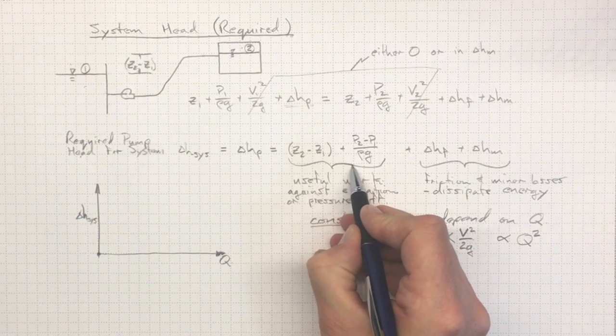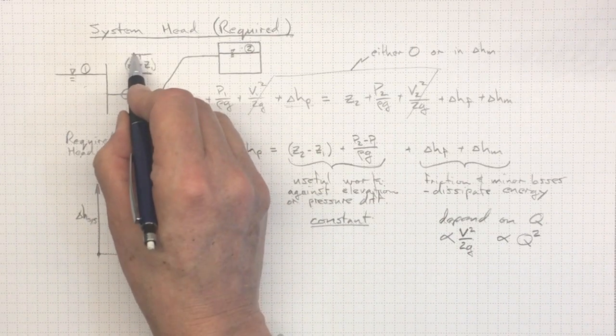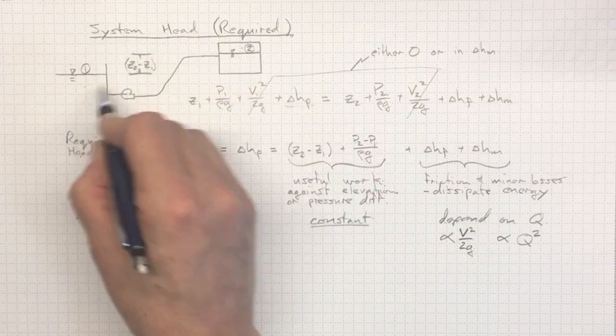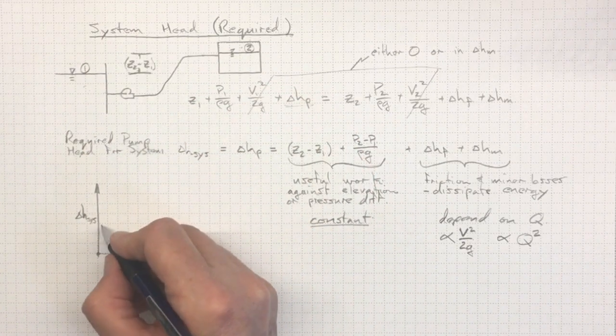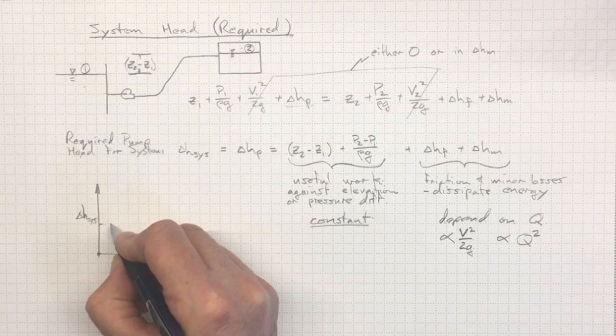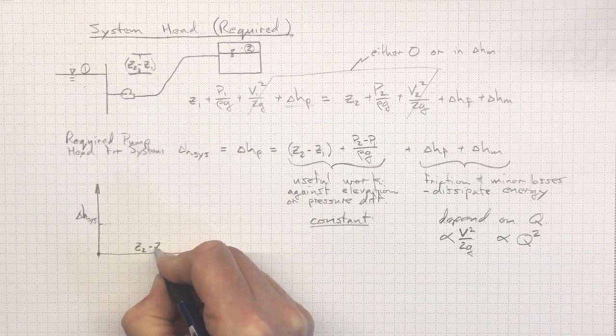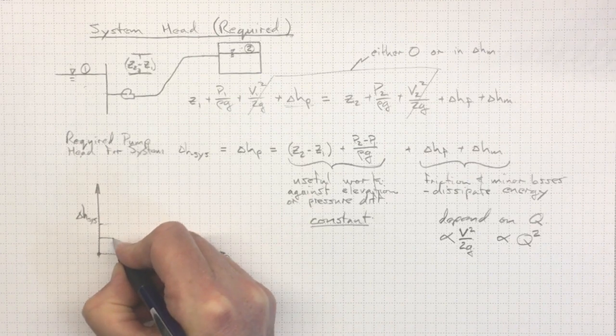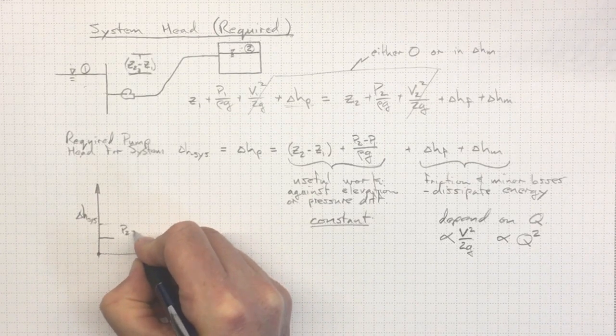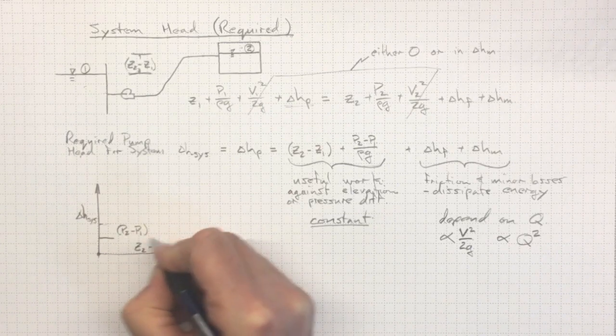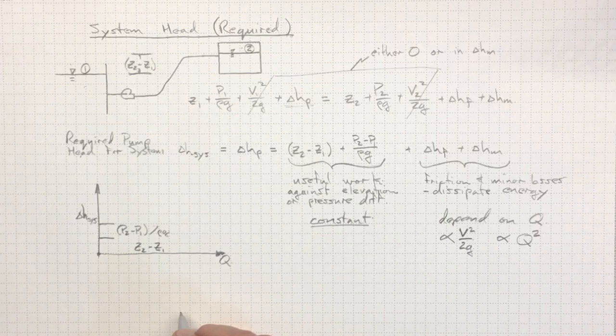But we'll still have to have enough head rise to overcome this elevation difference and this pressure difference before we'll get any flow at all. So, at low flow or no flow, we're still going to have to overcome Z2 minus Z1. So, let's say that's that much. And we're also going to have to overcome P2 minus P1 over rho G. Let's say that's that much.